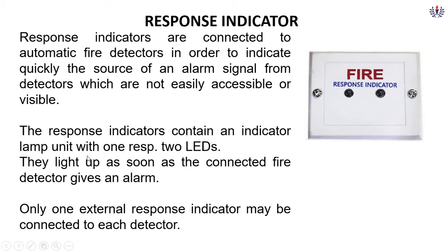The response indicator has two LEDs respectively. When the fire alarm system is connected to the panel, and if any fire has been noticed, immediately the response indicator will try to activate. Only one external response indicator may be connected to each detector. So I think in many malls we may see only one response indicator for all the floors.